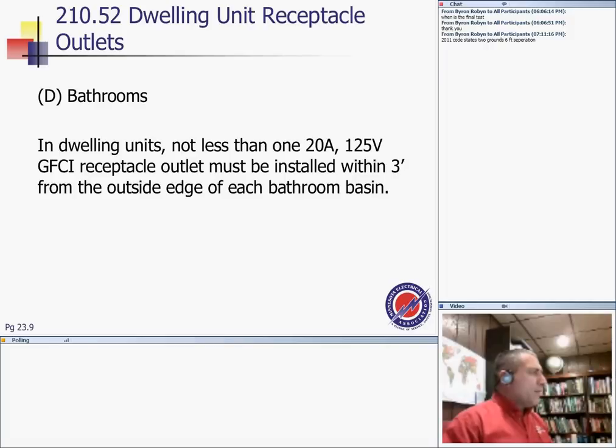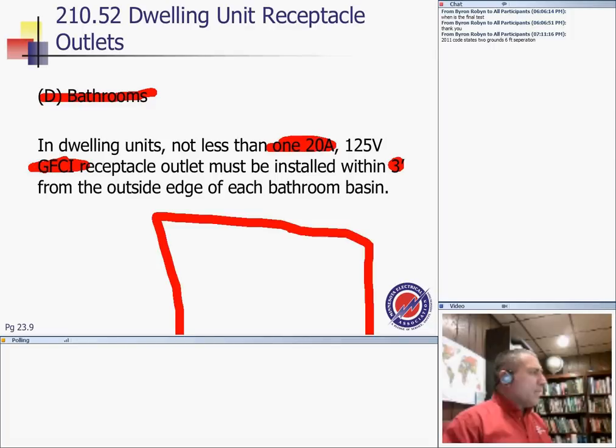Okay, bathrooms. You guys remember what we said about the bathroom? One receptacle fed from a 20 amp circuit within 3 feet of a sink, and GFCI. Always. I'm sure a lot of you guys remember that if you do residential. That's kind of like the alphabet of wiring. 20 amp circuit feeding one GFCI receptacle within 3 feet of a bathroom sink. Now here's a question for you guys. If I have a bathroom, here I have my receptacle here, an exhaust fan over here, and a light here.